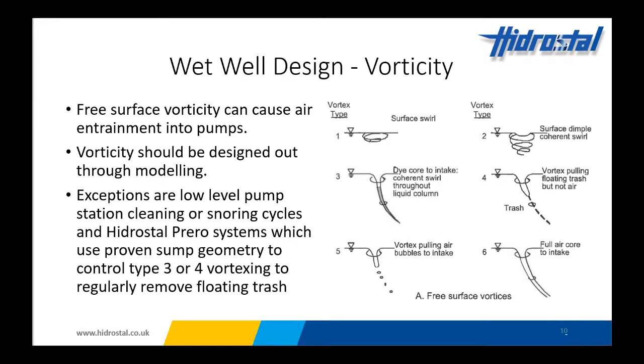Let's talk about vorticity now. The Hydraulic Institute classifies vortexes into six different types, as you can see here, from a surface dimple to a full air core. Free surface vortexes can cause air entrainment, particularly from type four upwards. So it's something you really do need to design out. Sometimes you have to model a station to actually ensure you're designing out surface vortices. There are exceptions, as there often are in wastewater. There seem to be few complete absolutes in the wastewater game.